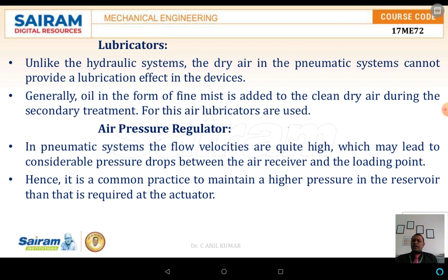The next part is the lubricators. Unlike in the case of hydraulic systems, where hydraulic oils are used as the working fluid and also as lubricants for the moving parts and actuators, here in pneumatic systems we are using air. The pneumatic systems cannot provide lubrication effectively because, due to compression or high pressures, there may be a rise in temperature. The rise in temperature may remove the lubricants from the moving parts. Generally, oil in the form of a fine mist is added to clean dry air during secondary treatment. For this, air lubricators are used.